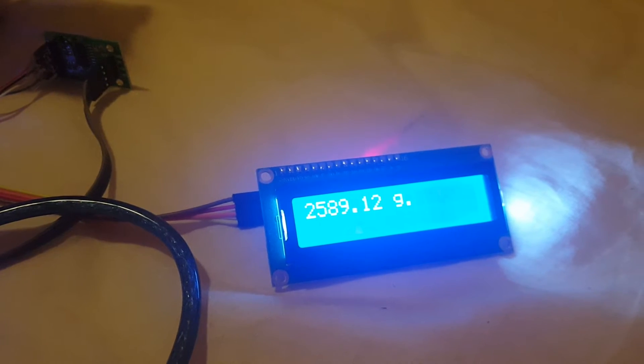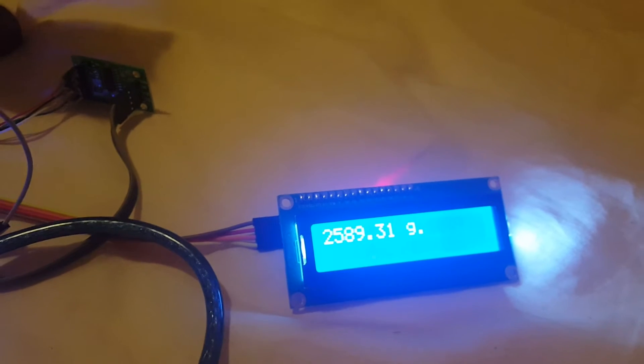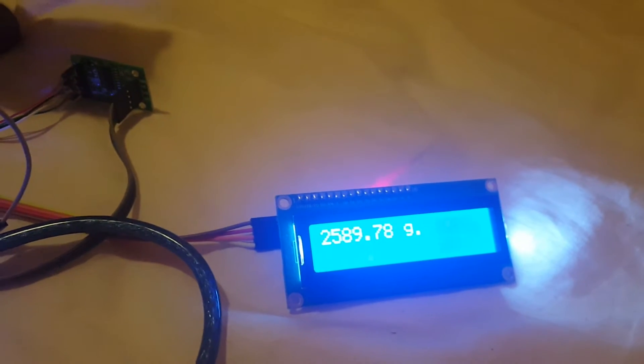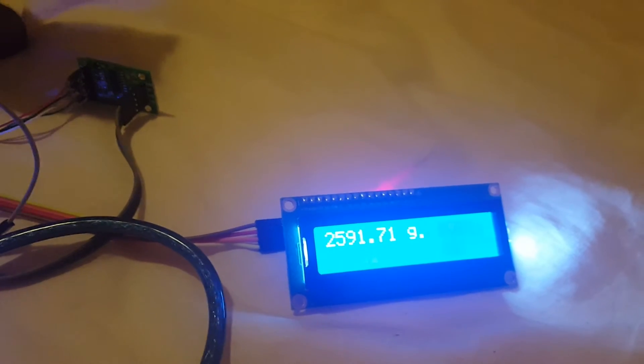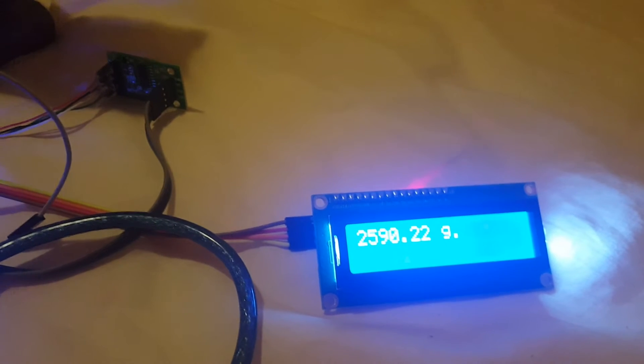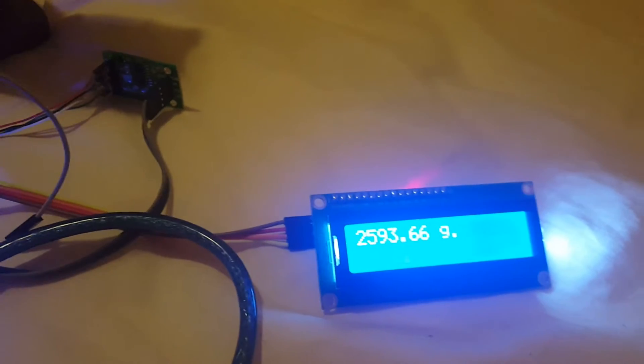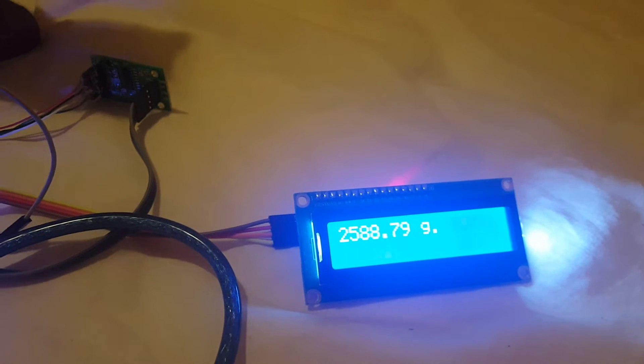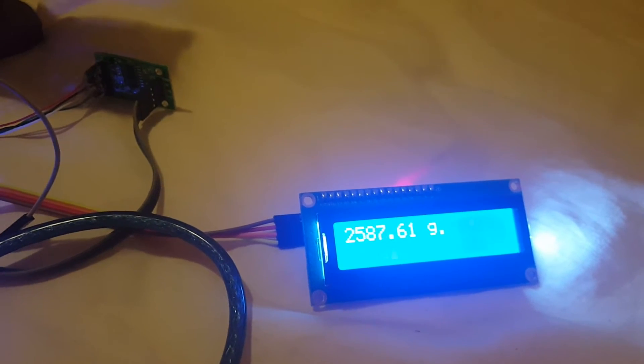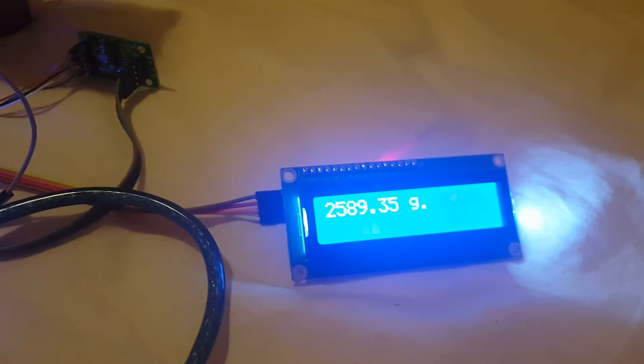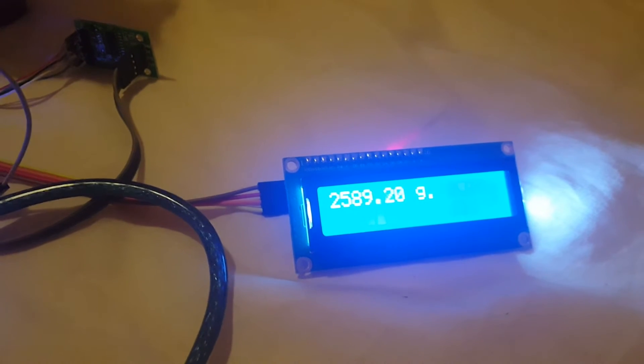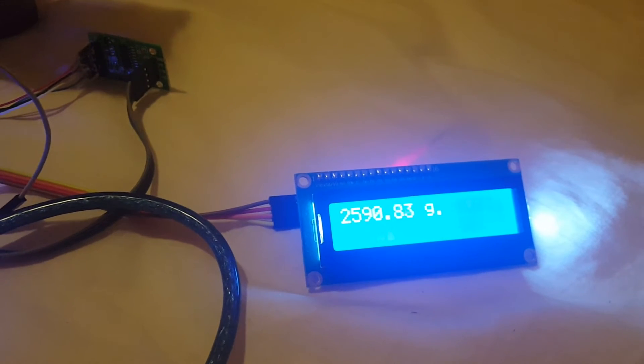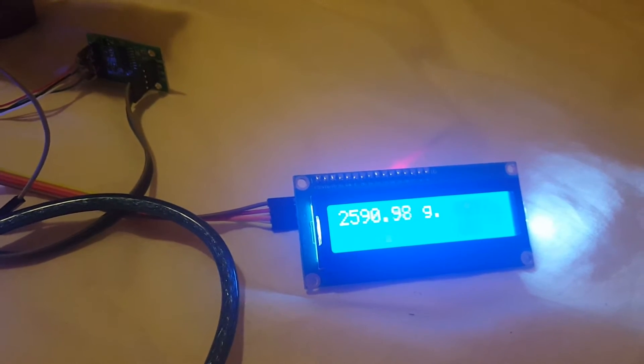I do not recommend that you use the 20 kilogram load cell for 0.5 gram display, because its accuracy is not enough. If you want to measure 0.5 gram, you need less capacity.